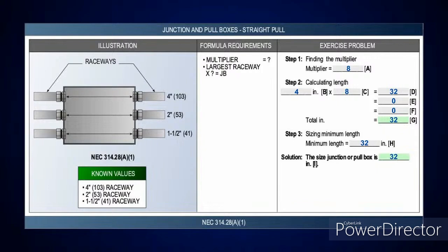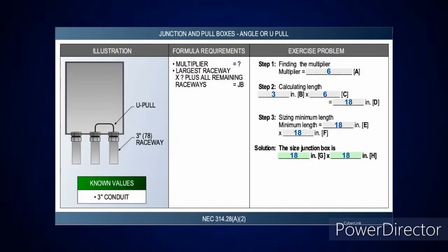For multiple raceways on a straight pull, it's the same calculation. Take the largest conduit — in this case a 4-inch — multiply by 8, gives you 32 inches. All the rest are zeros; you don't even add anything. So the minimum length across has to be at least 32 inches. For an angle or U-pull with the multiplier 6: a single 3-inch raceway means that box has to be 18 inches by 18 inches.